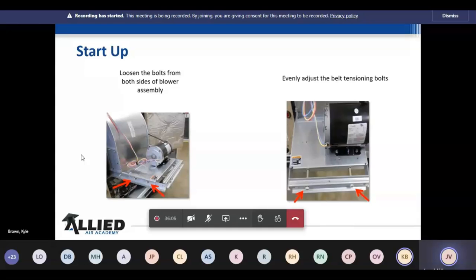Making sure you adjust these. Now I showed this particular example on here because you can pull this one out and you've got to loosen up the side bolts, and then you take the two front bolts that are over here and you back this out, but you've got to make sure this is even through here, because the next slide I'm going to show you alignment, and if this is out, it's going to throw your alignment out.